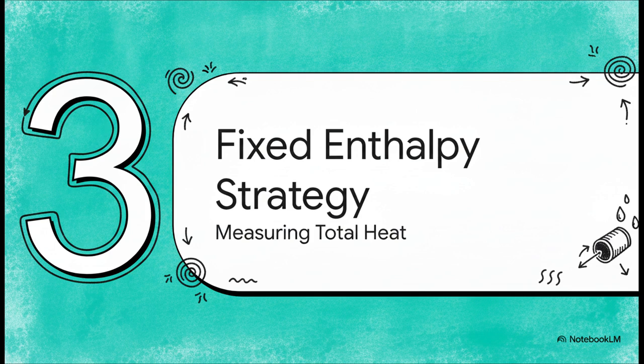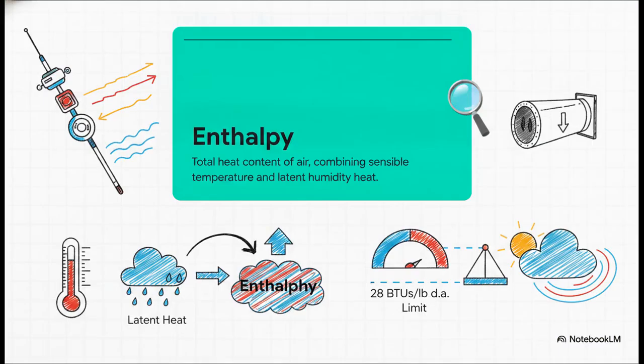Enter strategy number 3, the fixed enthalpy strategy, which focuses on measuring total heat. To make this work, we have to ditch that basic dry bulb thermometer for a much more sophisticated combination sensor. Enthalpy is essentially the total heat content of the air. It combines sensible heat, which is the temperature you actually feel, and latent heat, which is the moisture or humidity in the air. By measuring both of those together, this strategy compares the outdoor air's total energy to a fixed limit, usually somewhere around 28 BTUs per pound of dry air.